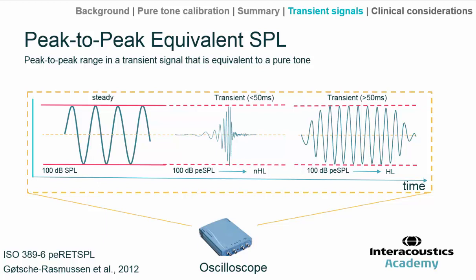Some transient signals used in evoked potentials are actually longer than 50 milliseconds — for example, commonly used slightly longer duration signals for N1P2 cortical evoked potentials, auditory late responses, and so on. In these cases, they can be calibrated and referenced to normal pure tone reference equivalent threshold sound pressure levels, and the usual dB HL label is indeed used.